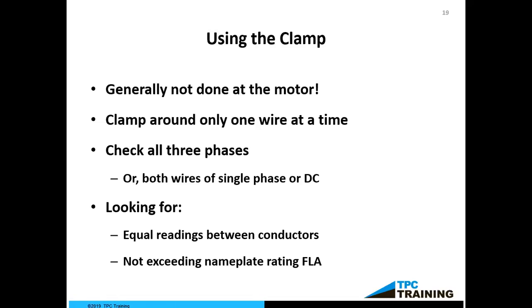And it's going to tell me how much current that motor is drawing. This is a great check, because if I'm overloaded a little bit, I might not have any physical indication to me. You know, it doesn't seem that the motor's running any hotter than it should be. Nothing has tripped off.